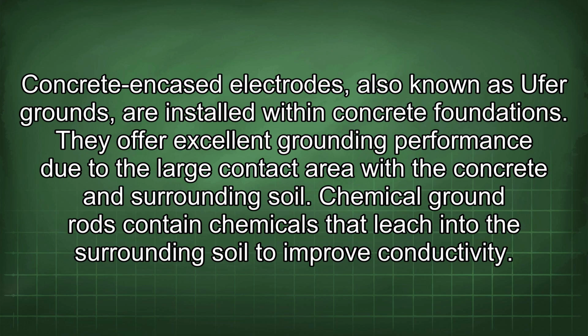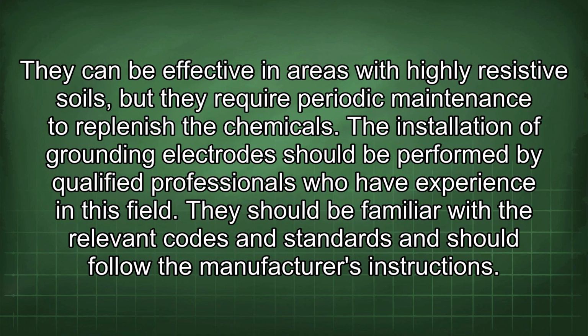Chemical ground rods contain chemicals that leach into the surrounding soil to improve conductivity. They can be effective in areas with highly resistive soils, but they require periodic maintenance to replenish the chemicals. The installation of grounding electrodes should be performed by qualified professionals who have experience in this field. They should be familiar with the relevant codes and standards and should follow the manufacturer's instructions.